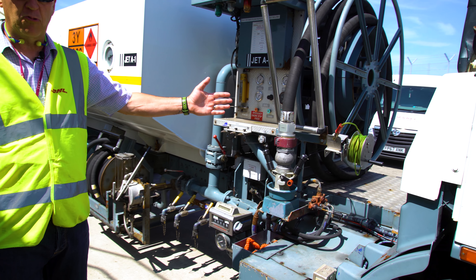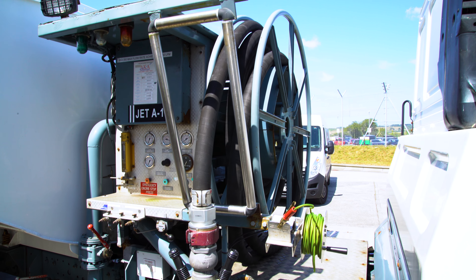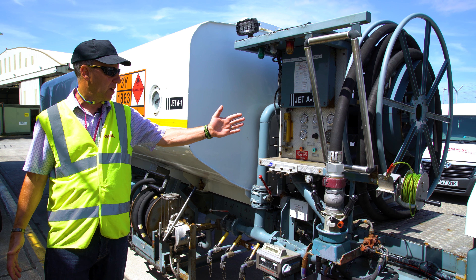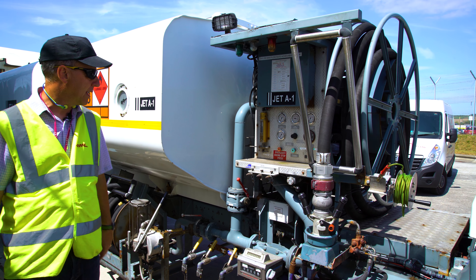The bonding reel must have 25 ohms maximum for continuity of the bonding lead. Correct hoses have a 10-year life, which includes two years of shelf life, and they must obviously be stored, manufactured, and installed correctly.